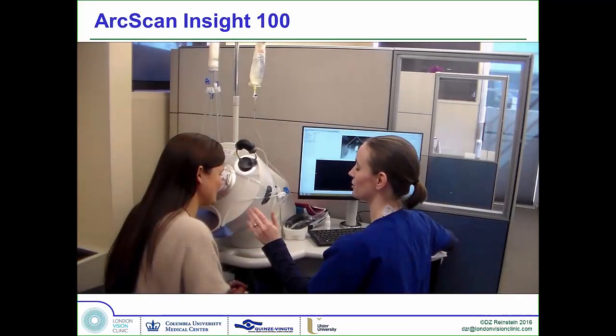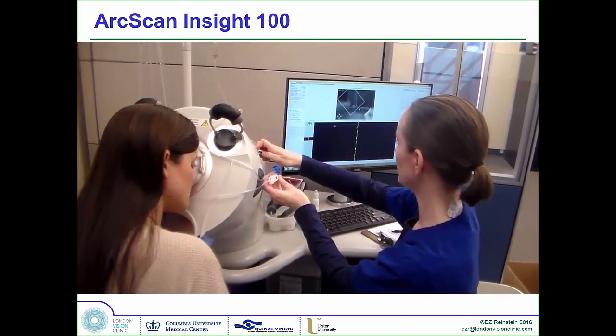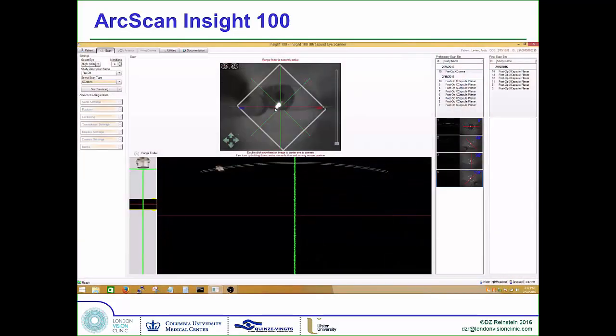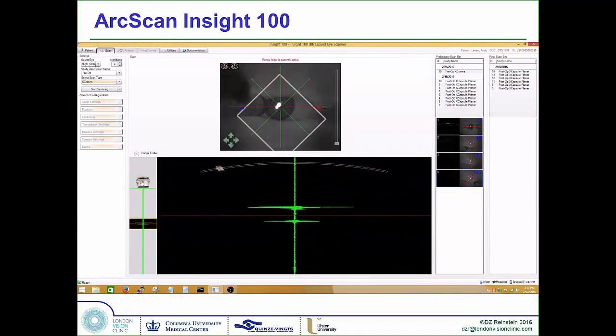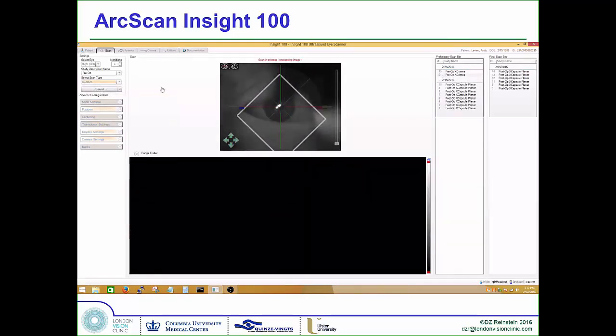The examination itself is very, very easy. The patient goes into a very soft, comfortable rubber eye seal. A little bit of water — about a few cc's — is put in. The cornea is ranged if you're doing a cornea scan, and then the device auto-senses the localization and does the scan sequence.